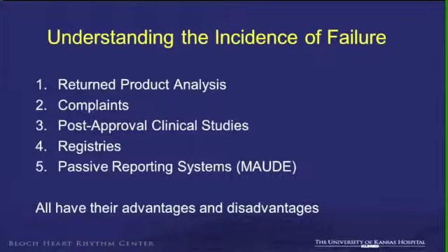The good thing about that is you can actually analyze in detail the products which have been returned. The bad thing is that very few products are actually returned. That has changed over time. Now more and more products are being returned, so that is improving, but that underestimates the real incidence of failure. Complaints, these are clinician complaints, are helpful if it's a rare incidence, if there are 3 or 4 happening across the globe and a complaint can help us, but overall they don't contribute much in identifying the incidents.